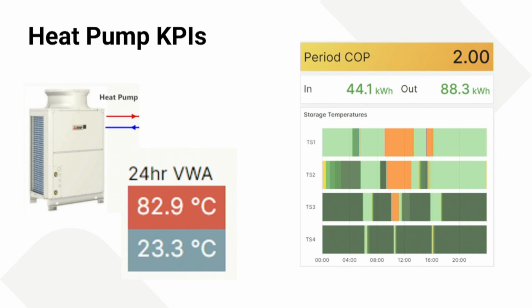Heat pump KPIs. So these came out of a job we did with Swansea, which was the world's first CO2 heat pump driven heat network. We were optimising the performance of CO2, which works better on nice high flow temperatures and nice low return temperatures. So these are the VWA temperatures for a day's operation. 82 degrees average flow, 23 degrees average return, which is unheard of low. I know 23 degrees for a VWA temperature is very low, but I'll show you why.